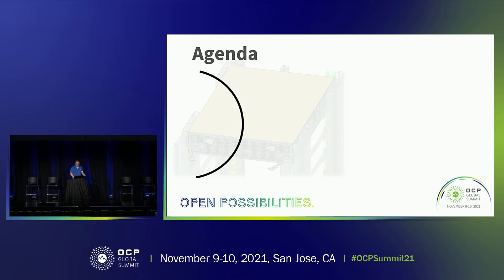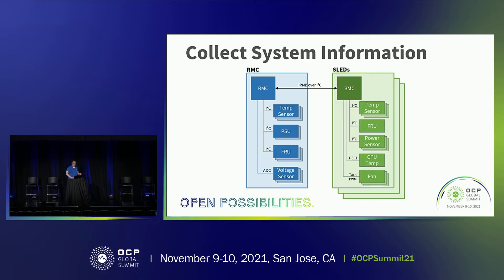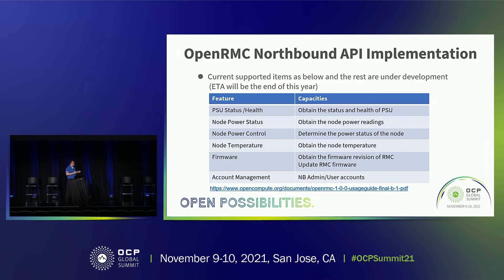Next, we'll talk about the northbound API implementation. As mentioned, the RMC collects various data for temperature, power supply status, and more through the IPMB. It also communicates with the BMC on each sled, including fan status. The RMC communicates back with the host via northbound API, providing status and controls for PSU status, sled power status and controls, and thermal information for each sled. In addition, the northbound API also has account management for administration controls.